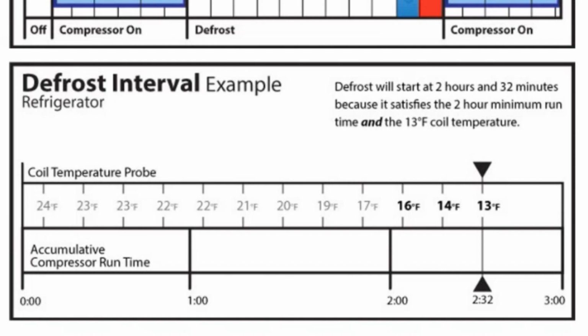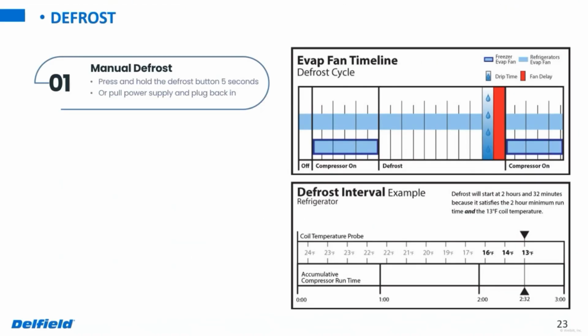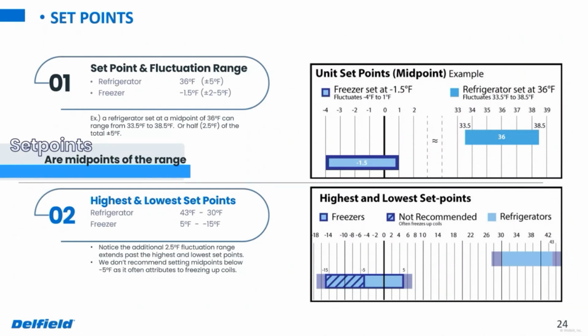So again, just to drive that point home, we have to have a couple things happen. First off, we have to have that compressor runtime of 2 hours, and then we also have to have the appropriate coil temperature at 13 degrees. The set points on these are typically going to be the midpoint of the cycle, and they're normally going to run about 2.5 degrees in either direction.